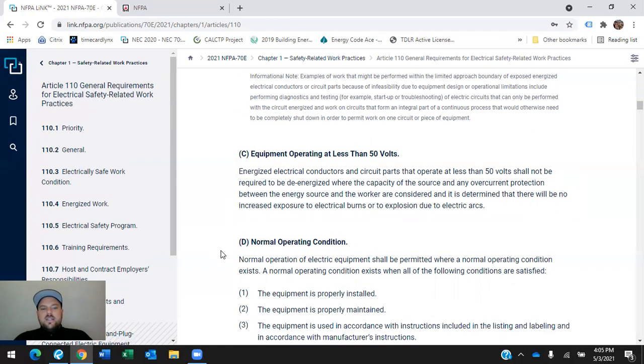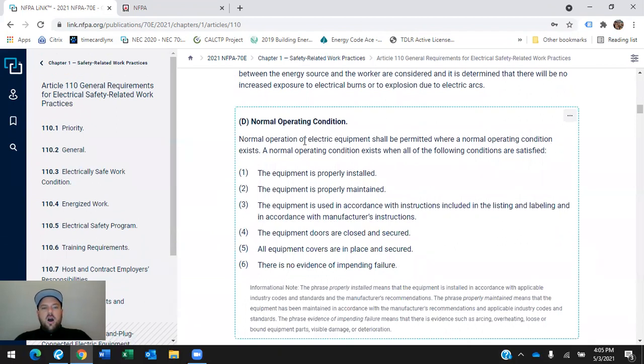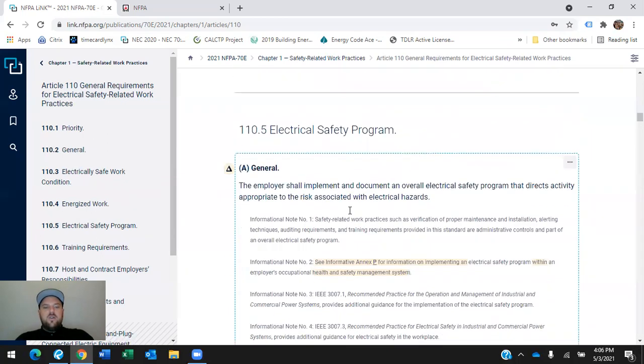Next, normal operating condition, D. Normal operation of electric equipment shall be permitted where a normal operating condition exists. A normal operating condition exists when all of the following are satisfied: the equipment is properly installed, properly maintained, and used in accordance with instructions included in the listing and labeling and the manufacturer's instructions. The equipment doors are closed and secured, all equipment covers are in place and secured, and there is no evidence of impending failure.